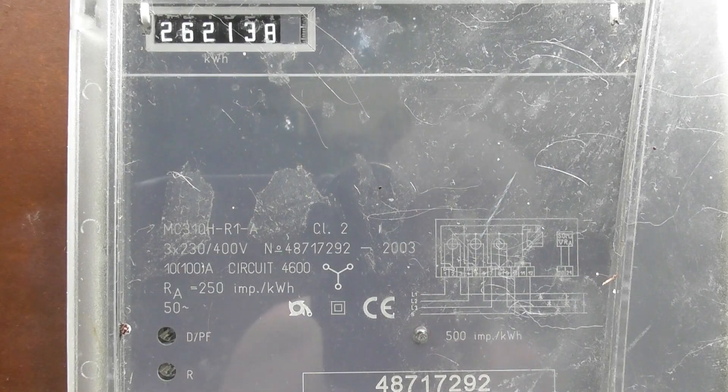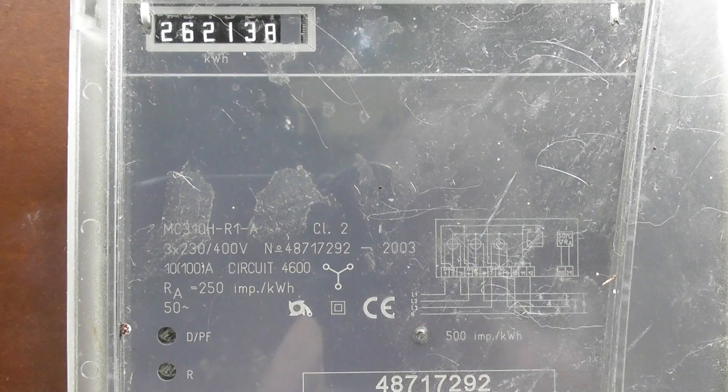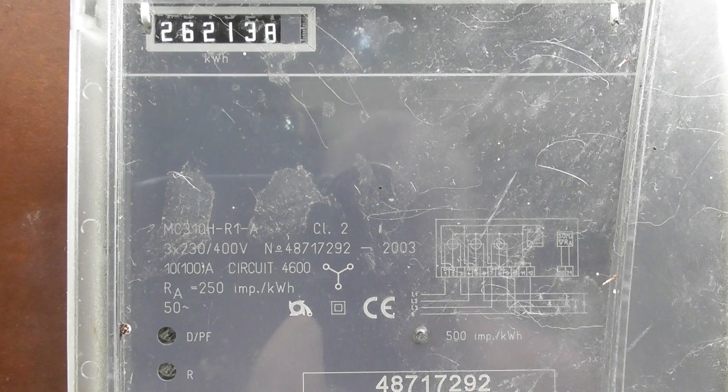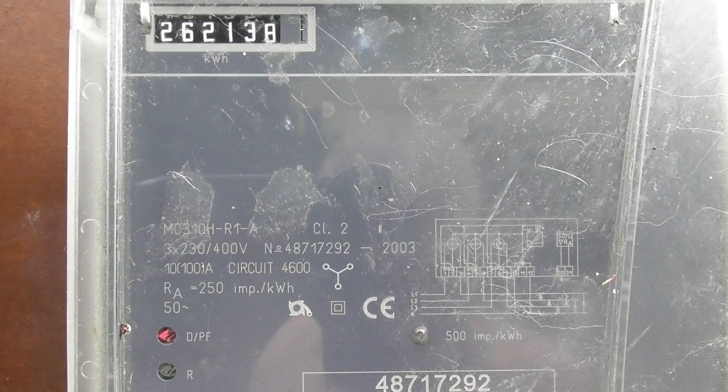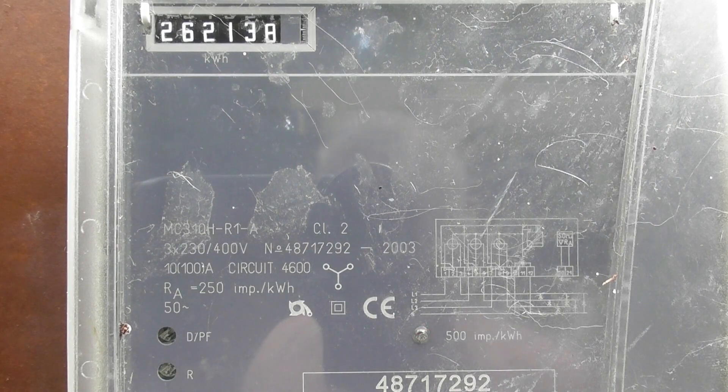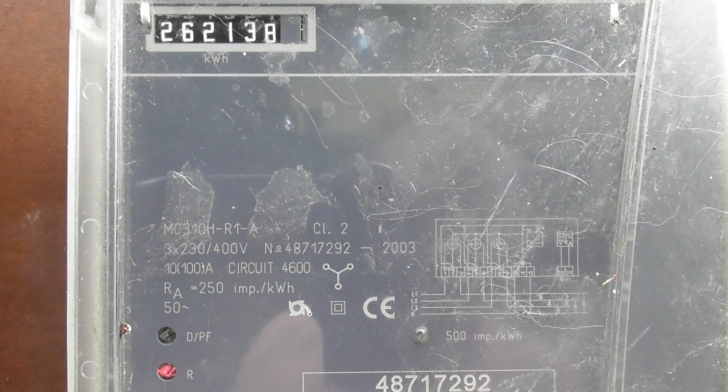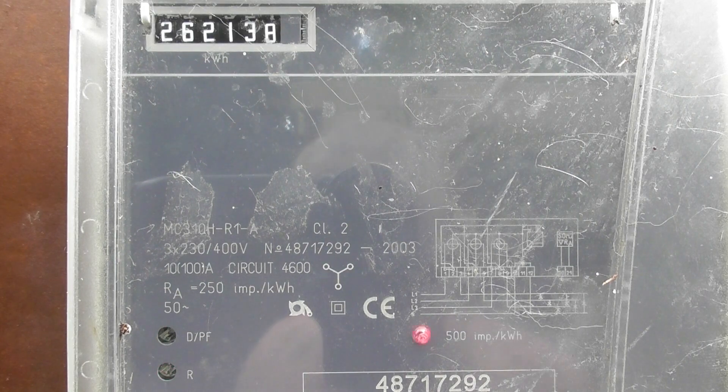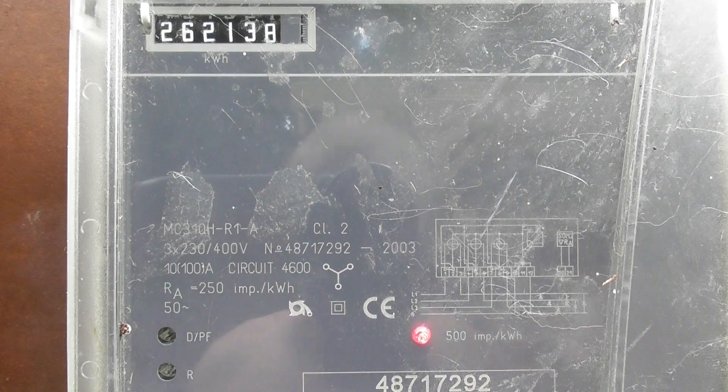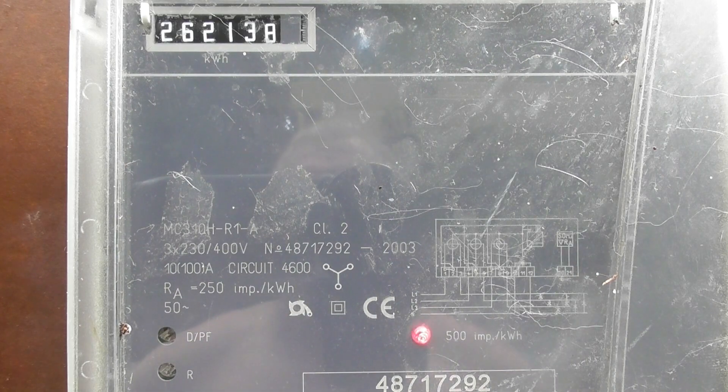Well, here we got a polyphase meter. And to go back to the reverse running stop, that has an alarm light which you will probably see glowing up here. It's an R for reverse. So I'll swap the polarity over, and that comes on straight away more or less. So some meters do have an alarm indicator to tell you that a reverse flow has occurred.